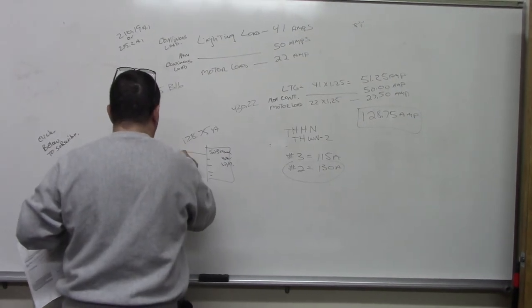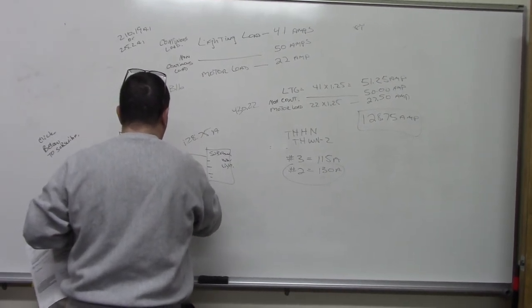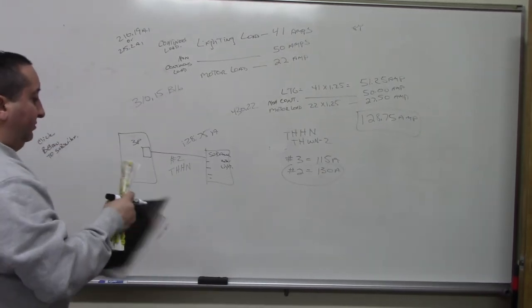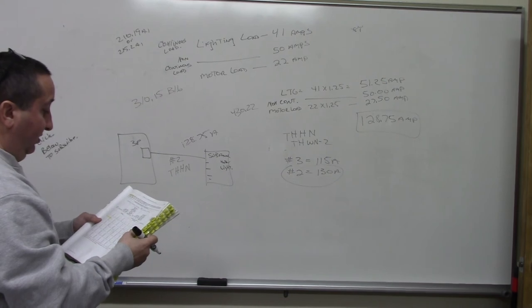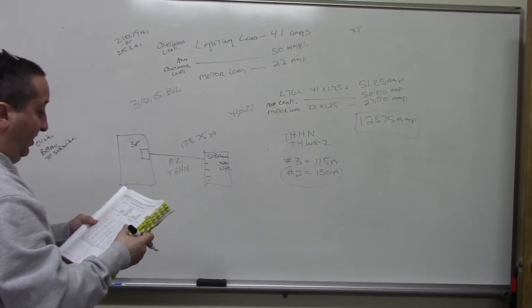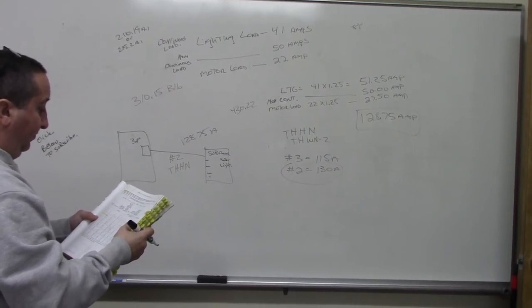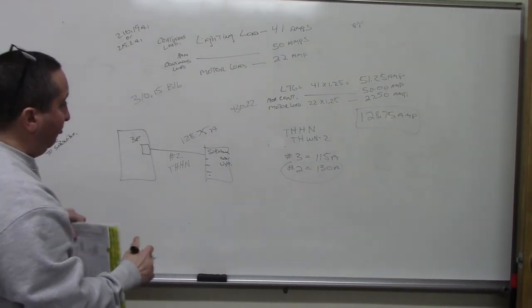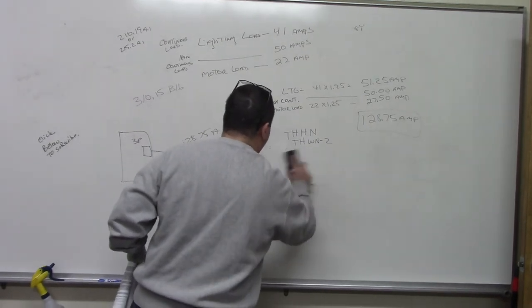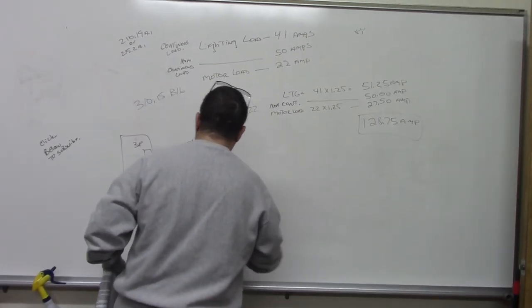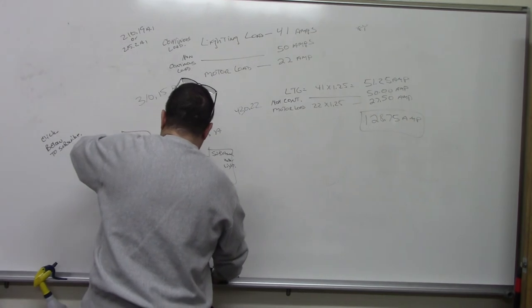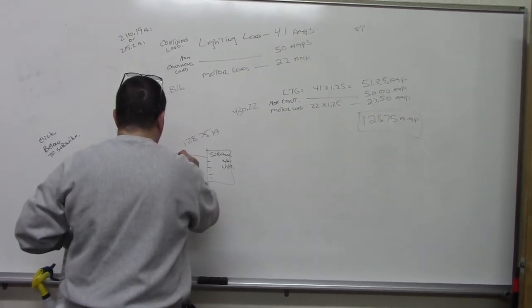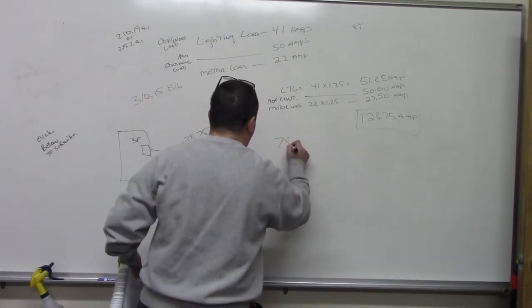A number 2 THHN. Okay? Actually, we could use it, but we can't use it because we have to be in a 75-degree column. So I am wrong and I apologize because there's no derating. So the answer is going to be, actually, the answer is going to be a number 1 wire. A number 1. Okay?